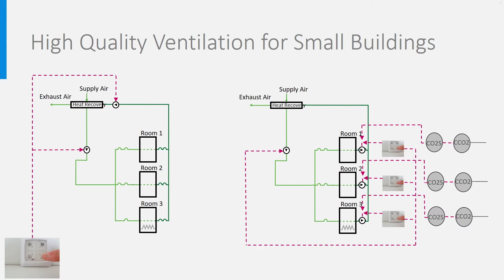It can be aided by CO2 control. A CO2 sensor, CCO2, measures the CO2 concentration. If the CO2 increases above a certain level, CO2 set, for instance 800 ppm, indicating too little ventilation, the ventilation will be switched on. There are also systems in which the supply ducts to the rooms are suppressed and the air is centrally supplied, in the staircase or corridor for instance, and it flows through a space under the door or through grills through the rooms in which the fan is on.